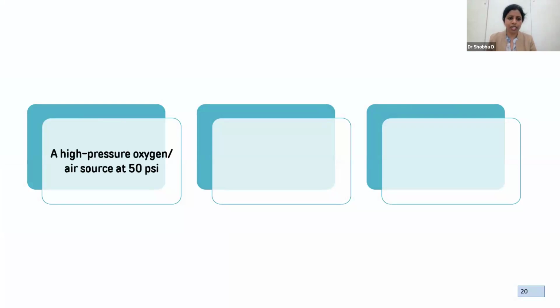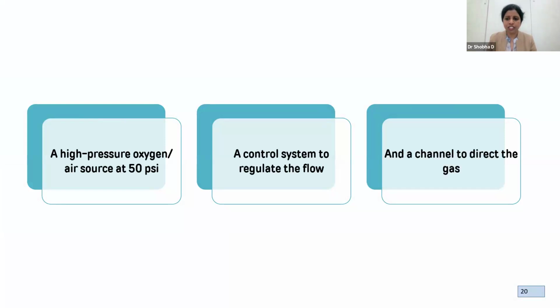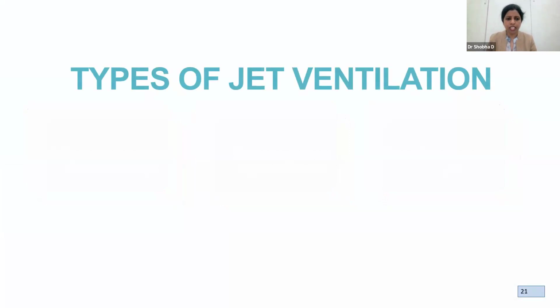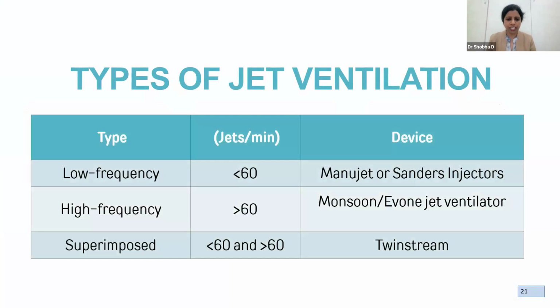So what do we need here? We need a high pressure oxygen air source at 50 psi, a control system to regulate the flow, that is a ventilator or a handheld device, and a channel to direct the gas in the form of a catheter or the cannula. So what are the different types of jet ventilation? As I said, we have the low frequency, less than 60 jets per minute, which is given by the Manujet or the Sanders injectors. High frequency, more than 60, by the Monsoon or the Evone jet ventilator. And the superimposed high and low frequency by the Twinstream ventilator.